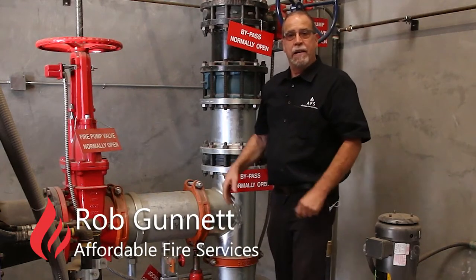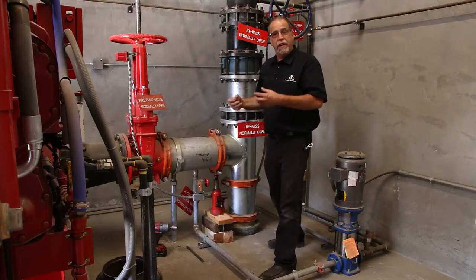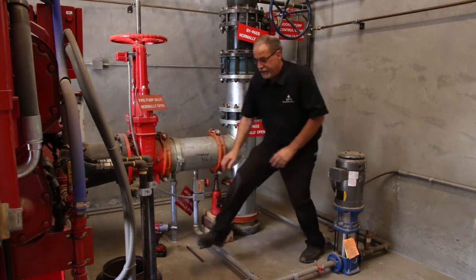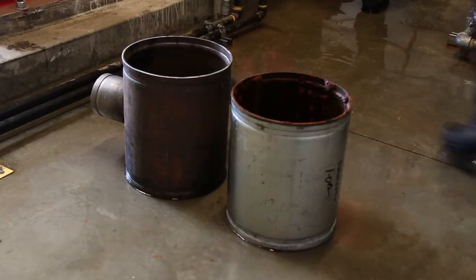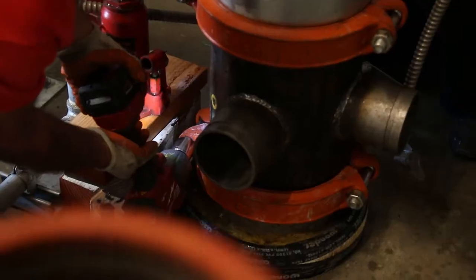I'm Rob Gunnett with Affordable Fire Services, and today we will be hooking up two portable fire pumps. We will be taking out this fitting and installing a fitting we had made up that will give us a source of water from the city utility to supply our fire pumps.